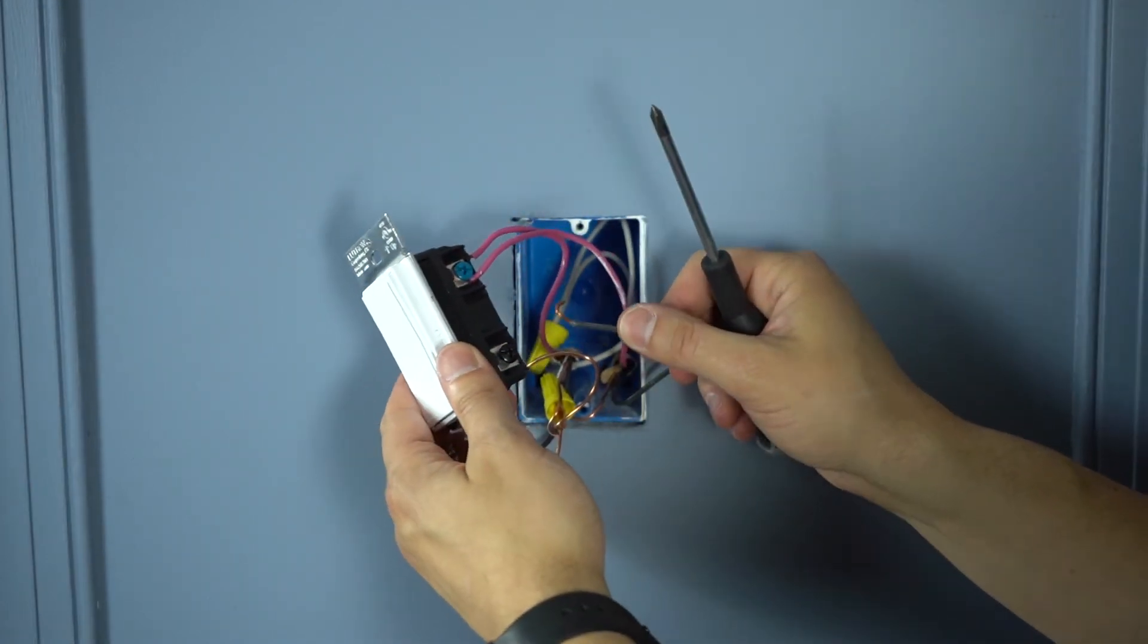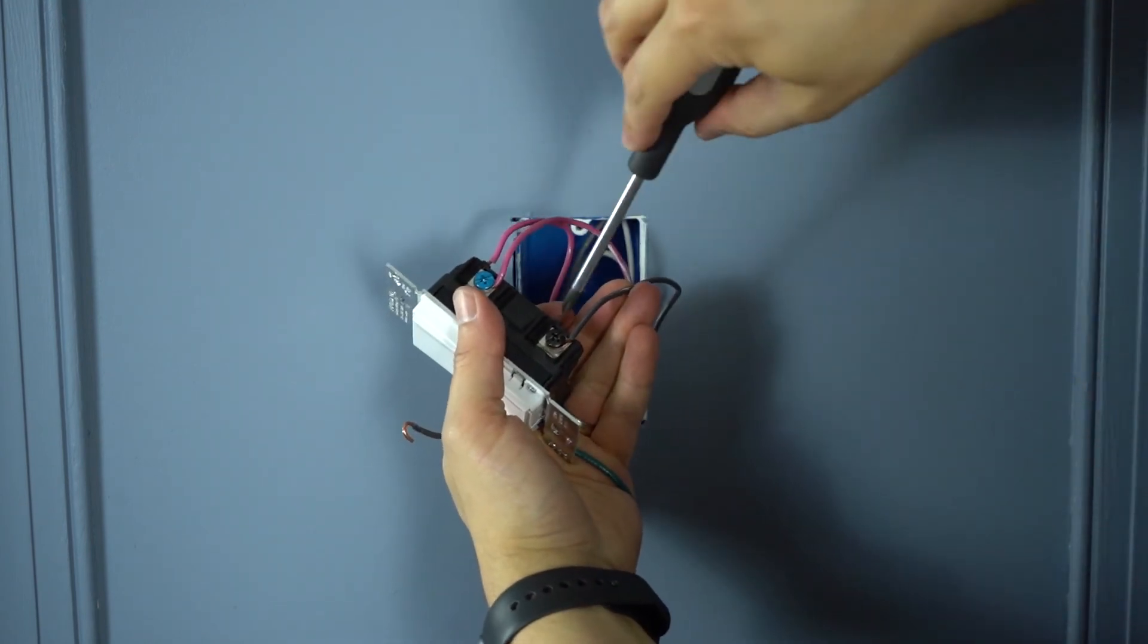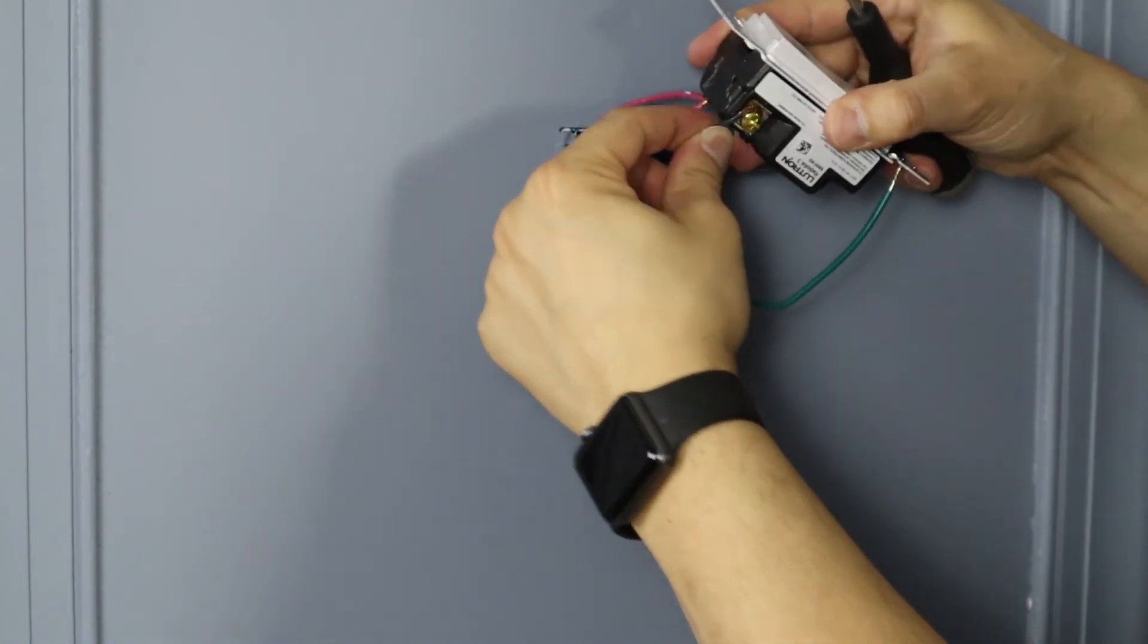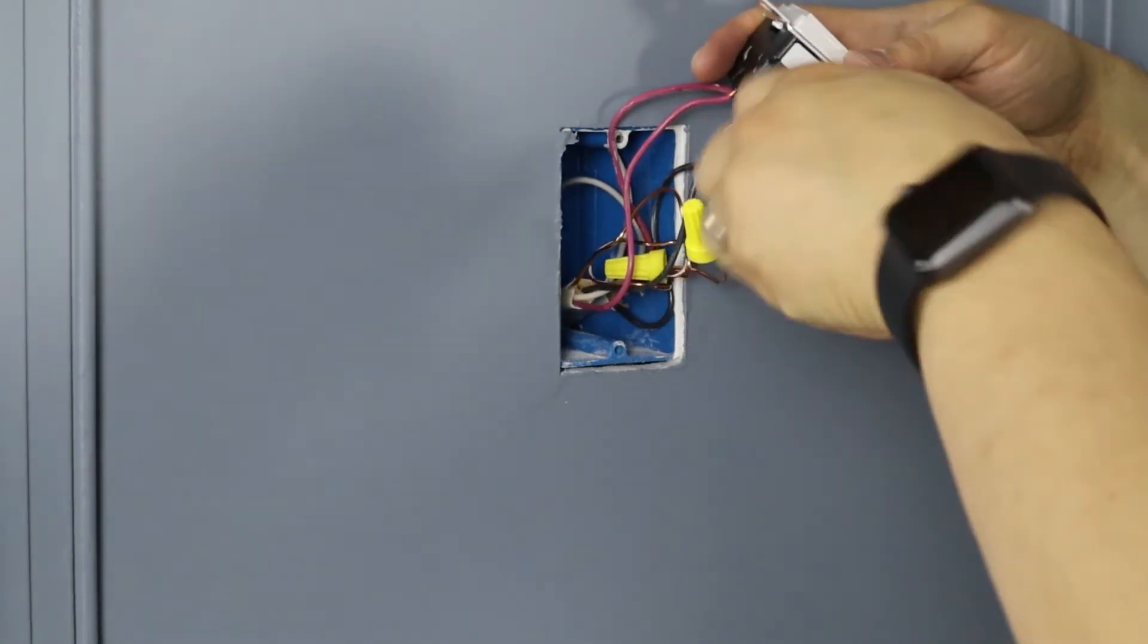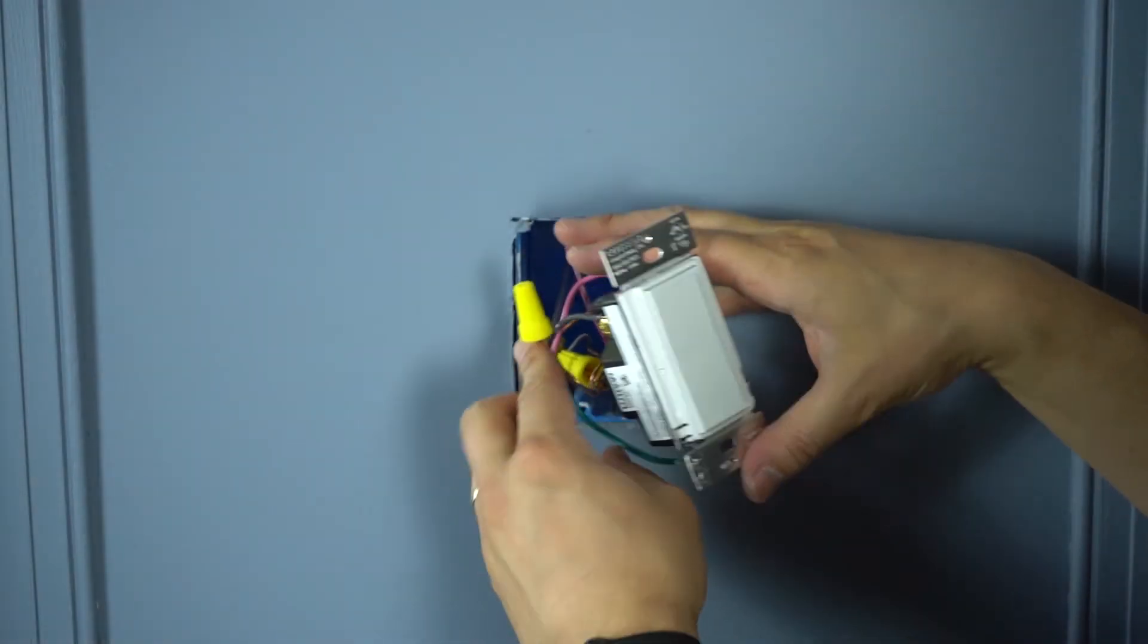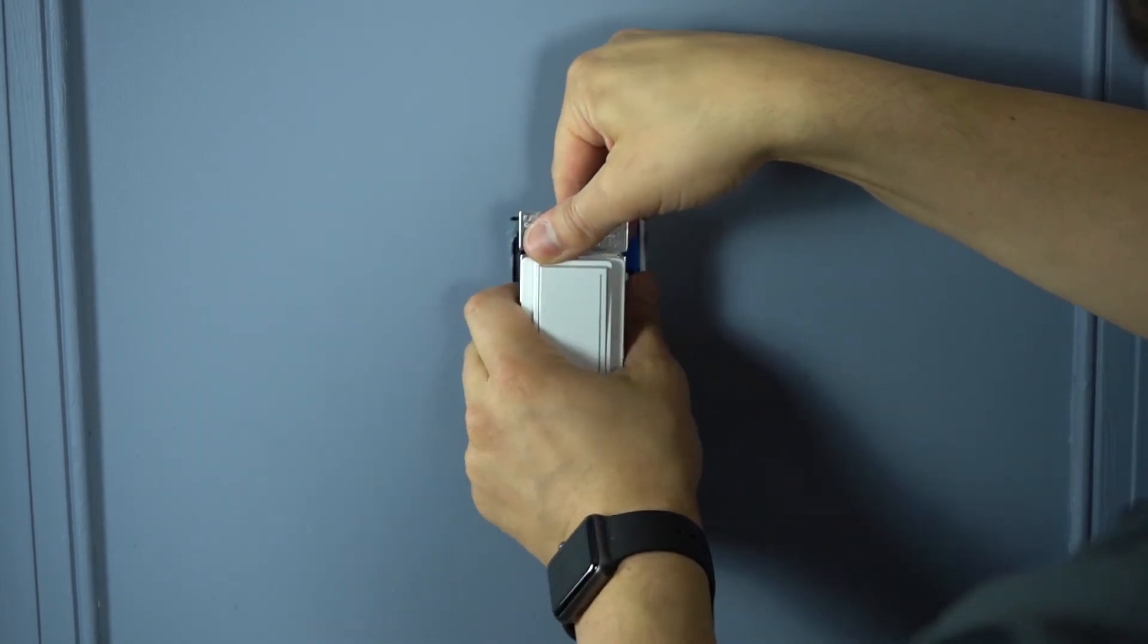Next, we're going to take one of the remaining travelers and tie it around the black screw. And the last remaining traveler will tie around the brass screw. Once the dimmer is wired, you can push the wires back into the wall and mount your companion dimmer to the wall box.